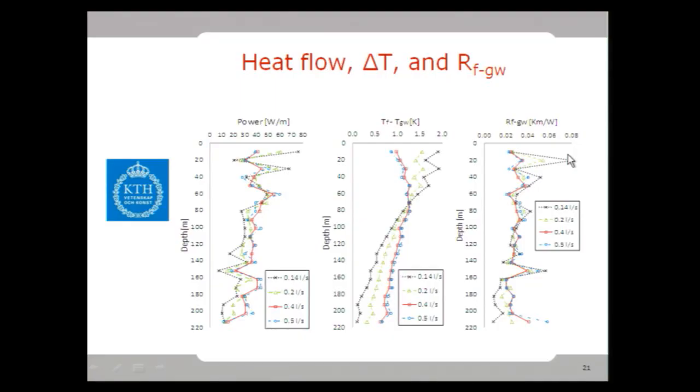And the temperature difference between the groundwater and the fluid that I showed you before, and these rates give us a picture of the fluid to groundwater thermal resistances along the depth, which you can see here for the different flow rates, resulting not to change much with the flow rate.